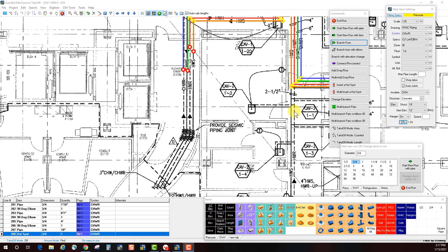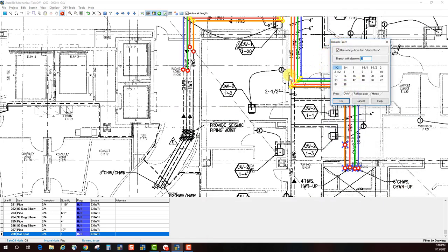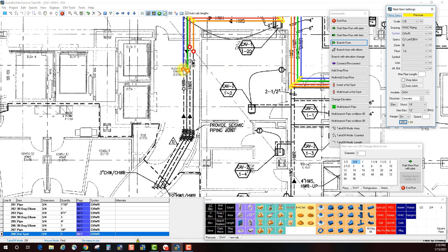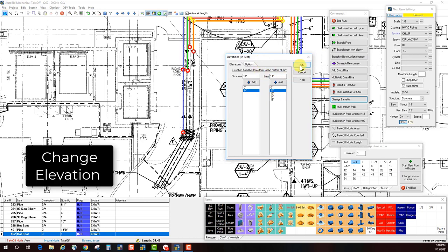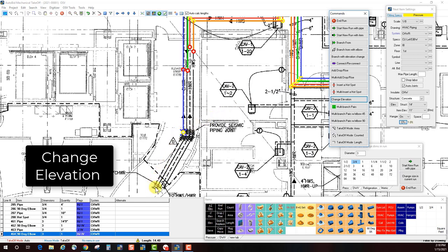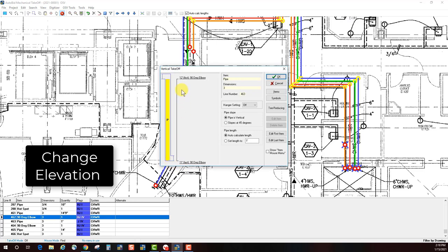Next, let's look at how to change elevations while taking off a pipe. I'll simulate an elevation change at a direction change, starting with Branch From, size three inch. After clicking the hot spot and continuing, when I want to change elevation I can use the Change Elevation command button. I pick 11 feet for the elevation change, hit OK, and an X appears. Reviewing the result: there's a 90-degree elbow at the first change, then a second one — the pipe dropped one foot.